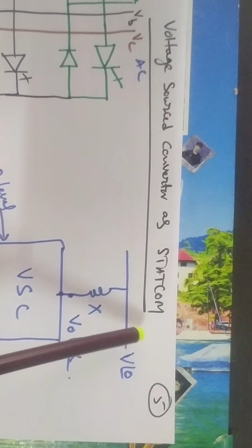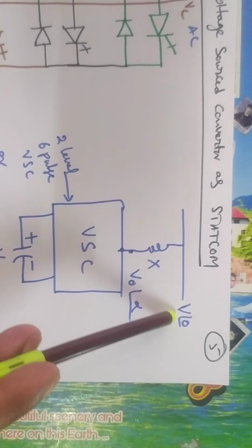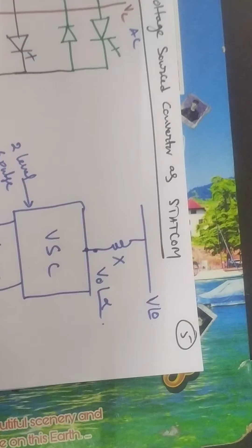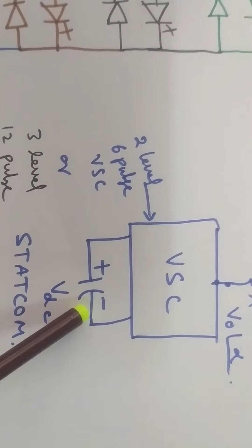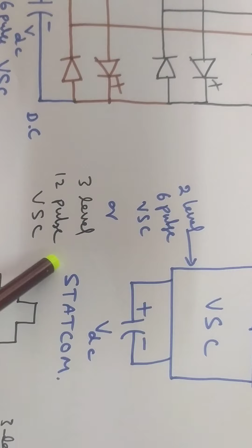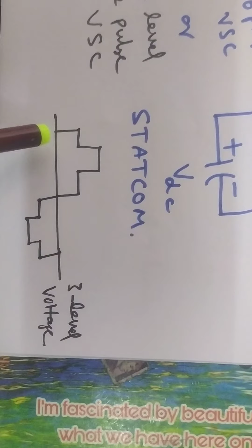So coming to the voltage source converter operating as STATCOM. So this is the VSC, V is the supply voltage, the bus voltage, and X is the reactance of the coupled transformer. VSC is the voltage source converter. This is the VDC, the DC voltage across the capacitance. It may be a 2 level 6 pulse VSC or a 3 level 12 pulse VSC, where the output of the 3 level VSC has 3 steps like this. Therefore, this is the waveform obtained from the 3 level VSC.